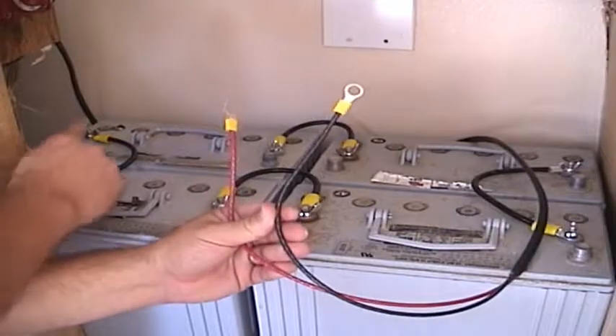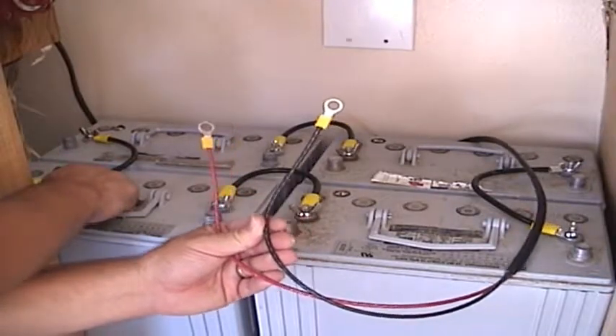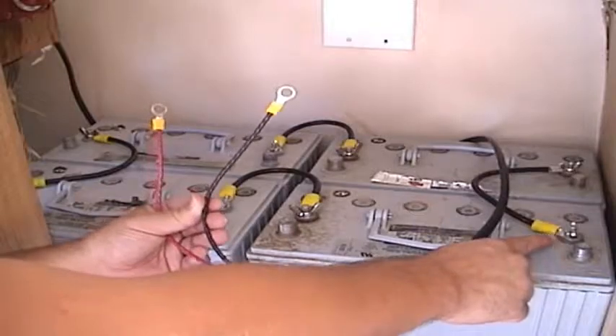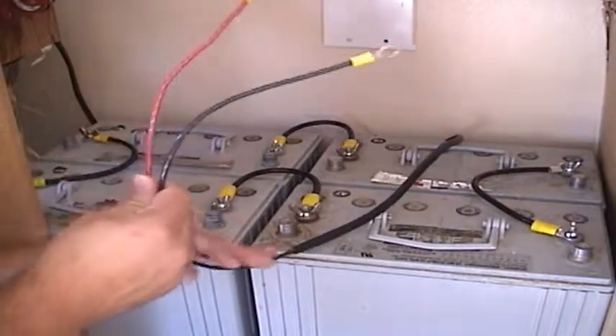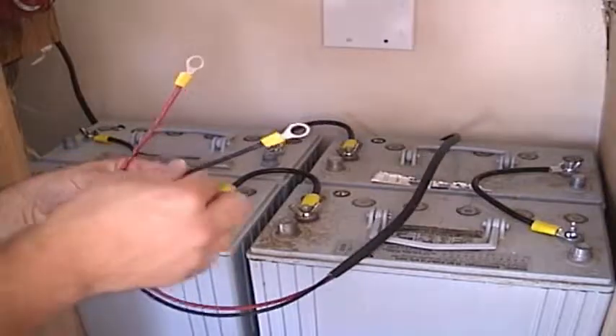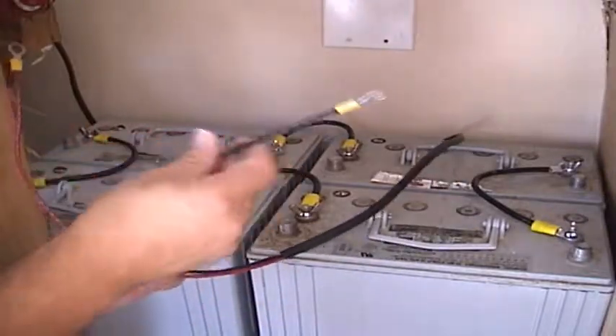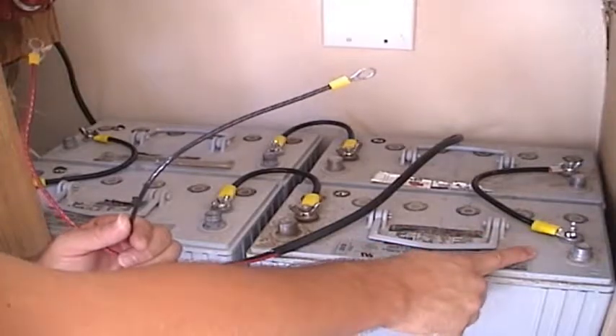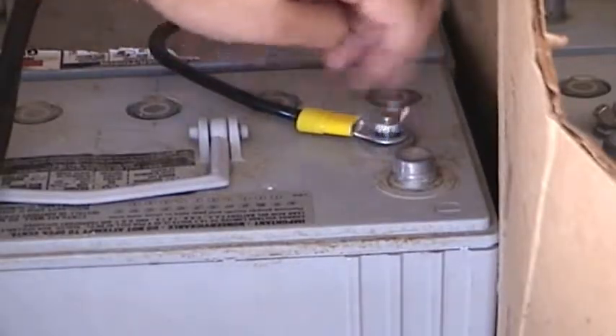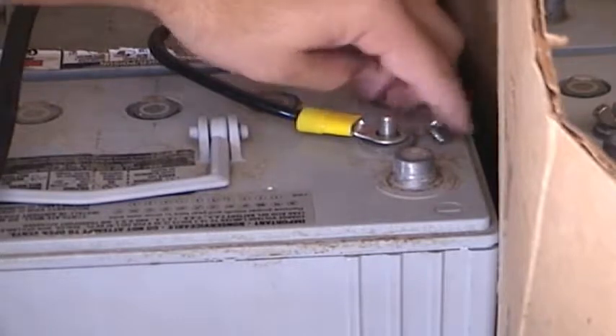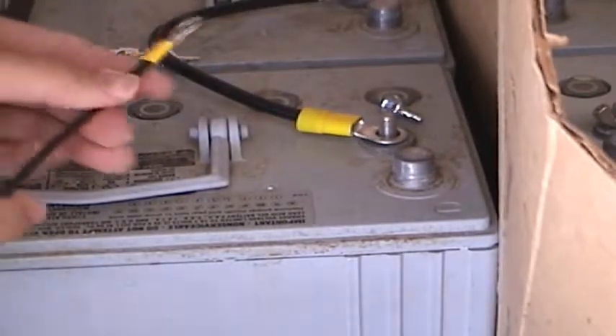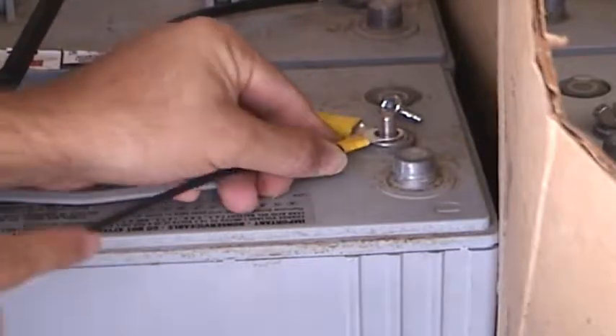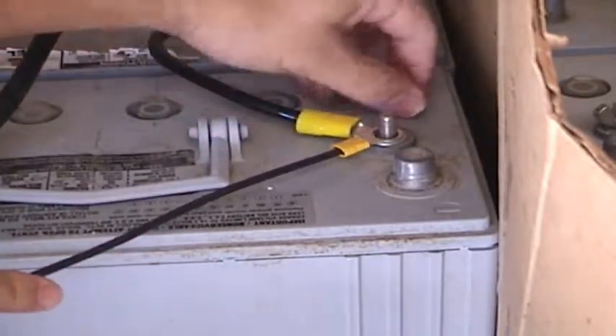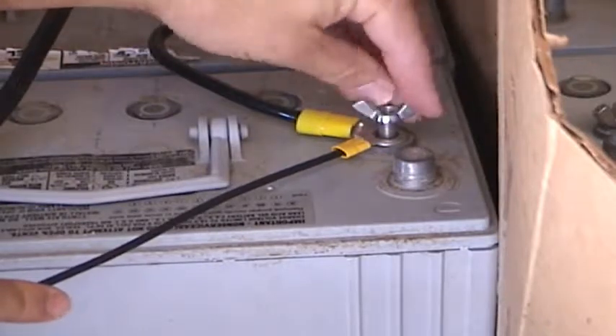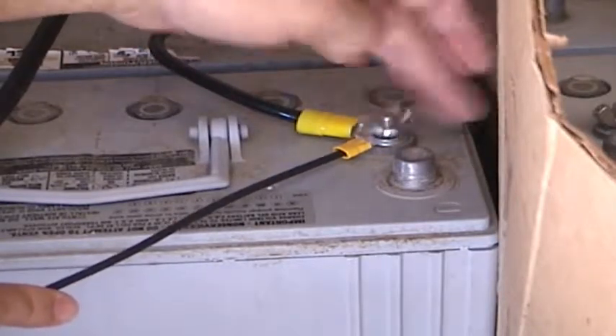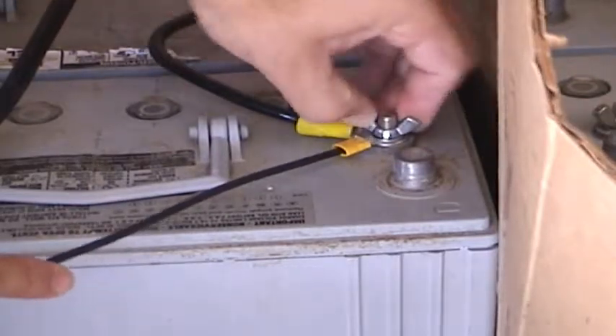Now let's go down to our battery bank. We have our plus 24 volts on this side and our negative on this side. Let's grab our black and red wire, and we're going to begin by connecting the black wire to the negative side of the battery bank. Let's go ahead and loosen the wing nut on one of the negative terminals. Get our black wire, insert the ring terminal, and replace the wing nut. Tighten it down.